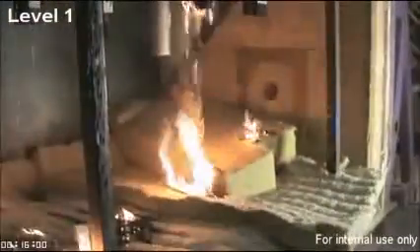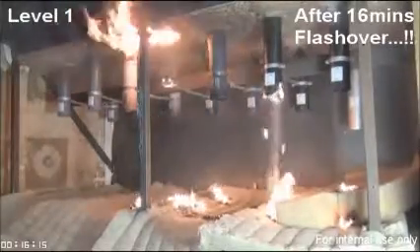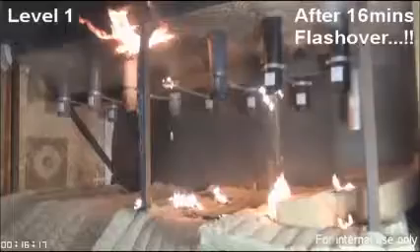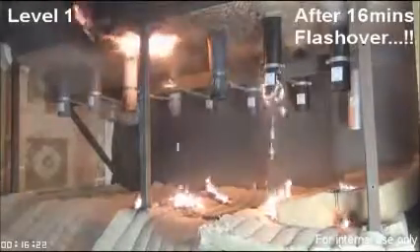You can see here in the close-up that burning plastic droplets are still dripping from the mid-deck. Meanwhile, the toxic smoke is still increasing, and most of the participants will now be forced to wear breathing equipment to avoid serious damage to their lungs and airways. Just over sixteen minutes have passed, as a waterfall of burning plastic from the PEH pipes creates a flashover.